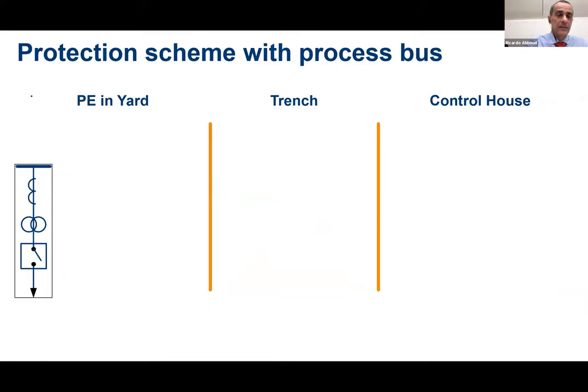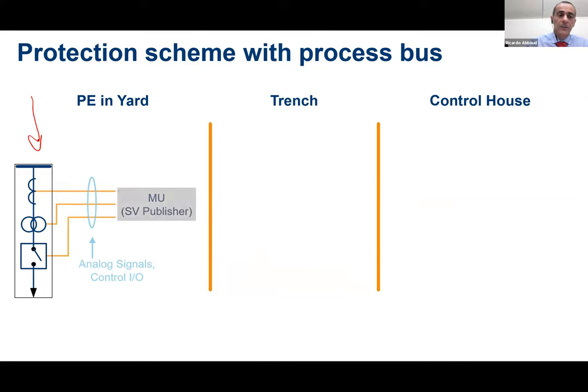So here I have in the switchyard the bay, the circuit breaker, the CTs, the PTs. I'm going to connect the CTs and the PTs to a merging unit. It's an electronic device, okay? It's not a protection relay. It's just getting voltage and currents. And also this merging unit has digital inputs and digital outputs to trip the circuit breaker, and also to get the status of the circuit breaker and the alarms and so on. So we have analog inputs for CTs and PTs, and digital inputs and outputs.